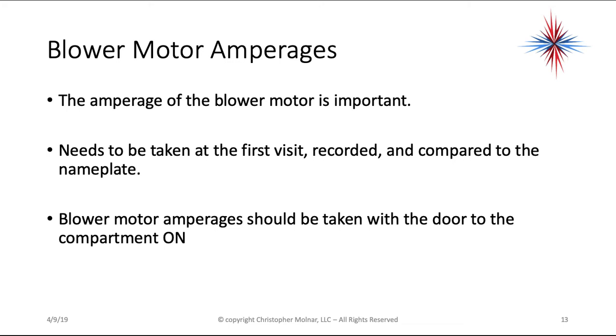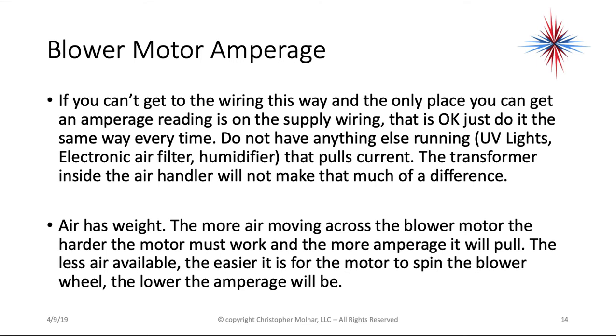Blower motor amperages are affected as well, and that's why we need to know them. The amperage of the blower motor should be taken at the first visit, recorded, and compared to the nameplate. Blower motor amperages should be taken with the door to the compartment on — taking it off does not give you the correct running amperage. If you can only access supply wiring, take the reading there consistently. Make sure nothing else is running — UV lights, electronic air filters, or humidifiers that pull current. Air has weight: the more air moving across the blower motor, the harder the motor must work and the more amperage it pulls. The less air available, the easier it is for the motor to spin and the lower the amperage will be.